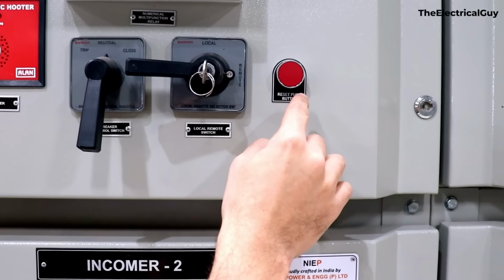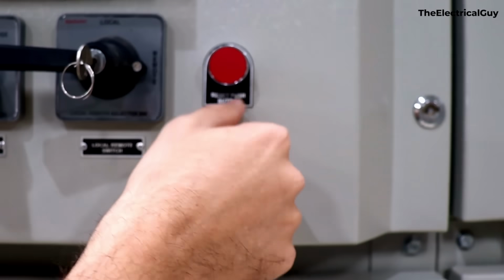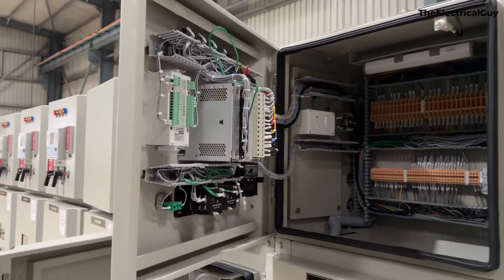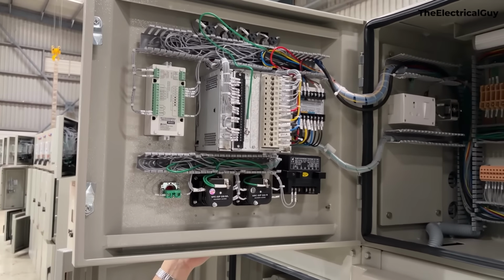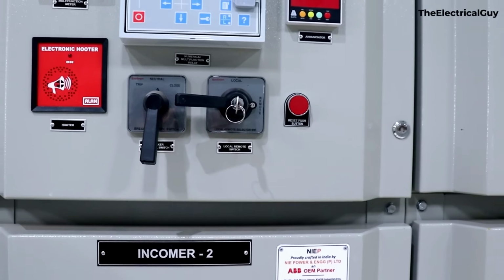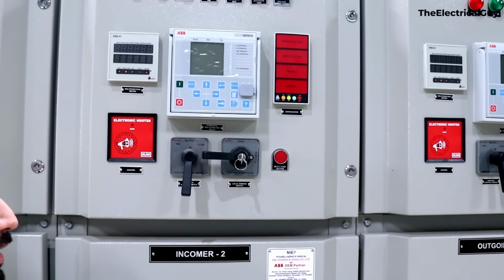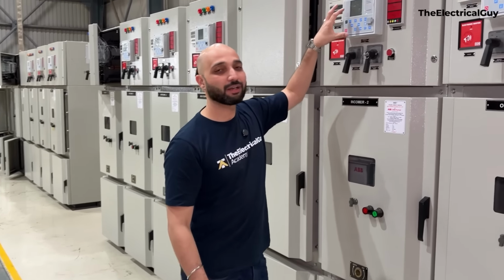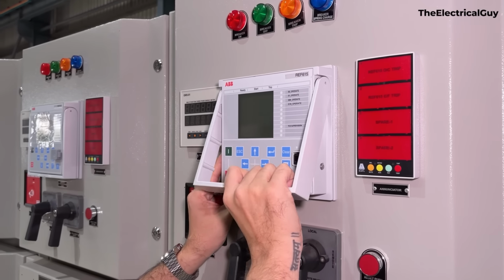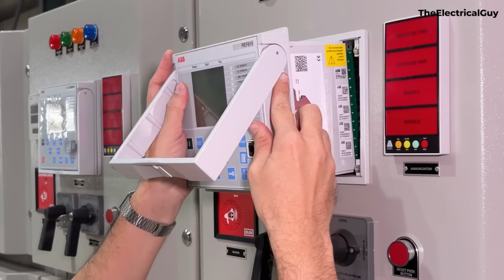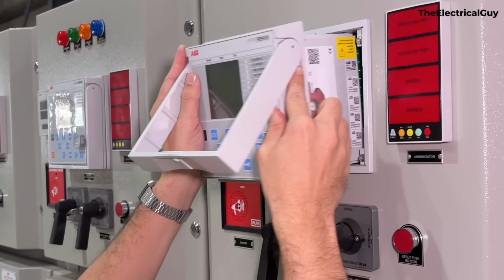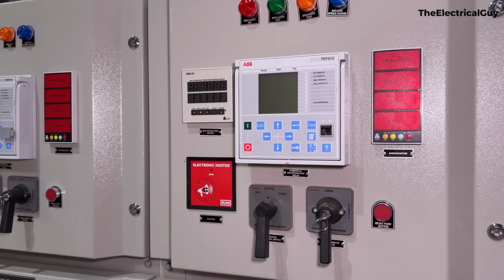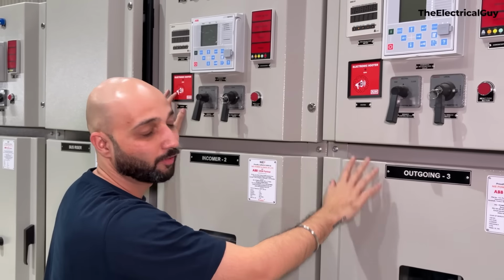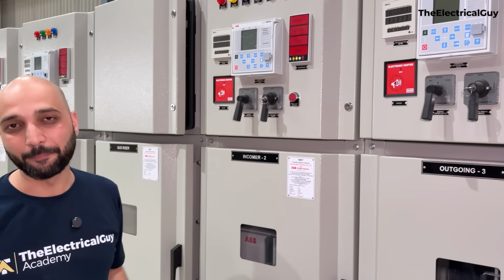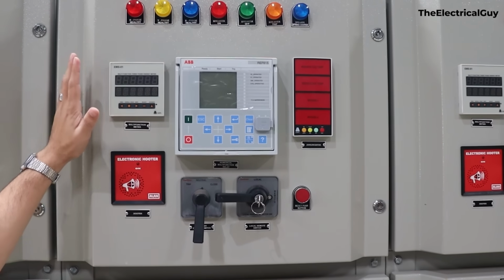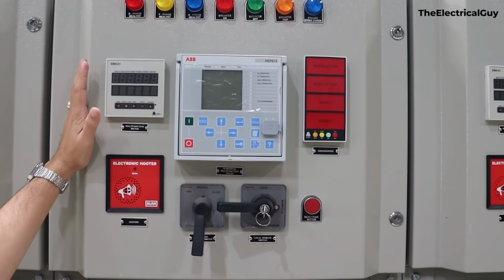And the last one is the reset push button, which is connected to our relay. So in case the breaker trips and you want to reset it, just press this push button and the relay will be reset, and you will be able to close the circuit breaker and the current will start flowing again. So we have here the relay. This relay is withdrawable. That means you can remove it when you want and then put it back when needed. Now this is super important when, let's say, the relay of this particular panel has gone down. You can take out this relay, put it back temporarily and solve the issue. So this is a withdrawable type relay. So that's everything that you see on the low voltage side, or the metering and relay chamber side.